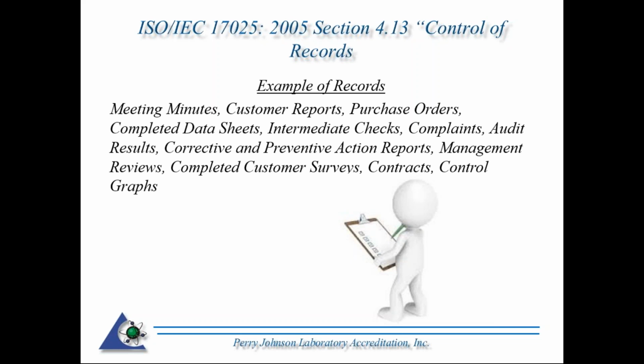Audit results, when you do your internal audit, say you're doing it to fulfill the annual requirement that you have within your QMS, Quality Management System, and to comply with 17025, the actual internal audit is considered a record. Corrective and preventive action, management reviews, completed customer surveys, contracts, control graphs. All those would be considered records and would come under the realm of Section 4.13, Control of Records.